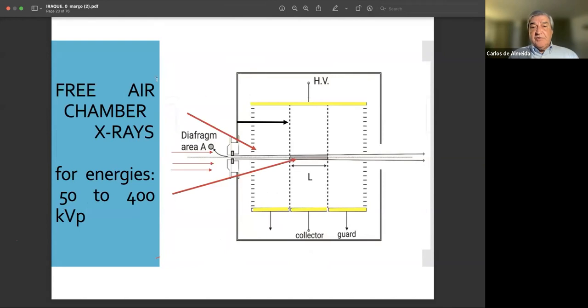What is a free air chamber? A free air chamber is a big box. It's a metal box with a collector and two guard rings, and the high voltage is equally applied to all three. The radiation field comes into a diaphragm that collimates the beam. It passes through an air layer with this dimension, which is the layer required to provide the electronic equilibrium. And this volume here, L, is the volume where you collect the ions produced by this amount of air.